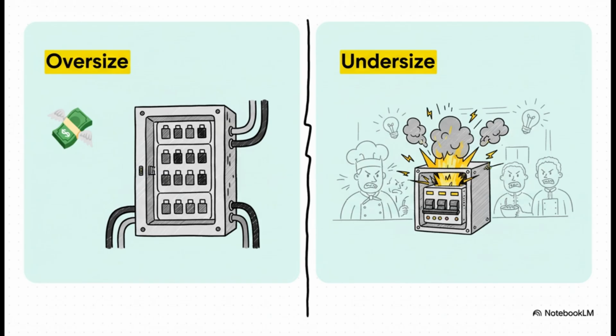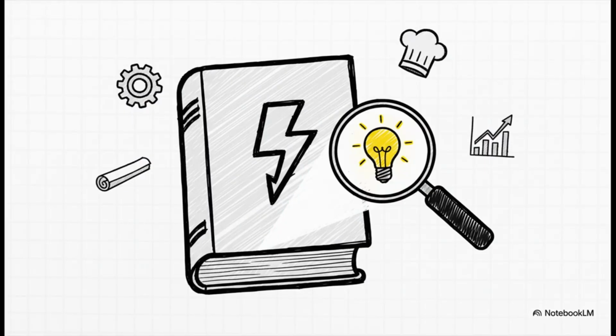But whenever the code gives you an optional path, there are always some rules attached. Always guardrails. So what are the key safety things we absolutely can't skip, even with this shortcut? Good question. The code is clear. You simplify the calculation, not the fundamental safety. For instance, protecting the service conductors against overload. That still has to follow sections 230.90 and 240.4. Okay, so the shortcut helps size the wires based on expected demand, but the actual protection, the breakers, the fuses, that's still based on the wire's limits and fault currents. Makes sense. Precisely. Basic system protection isn't optional.